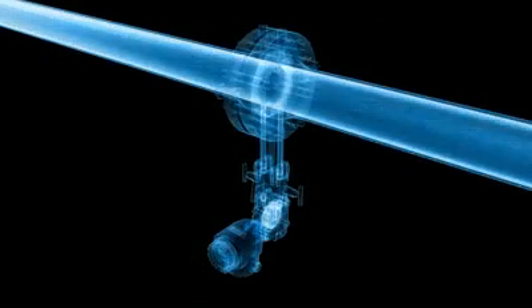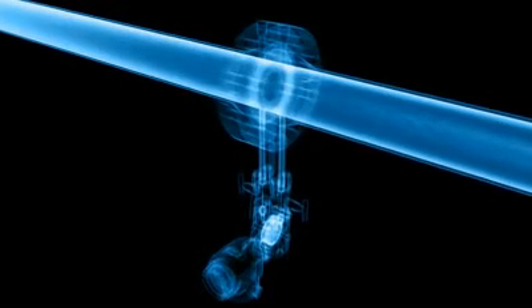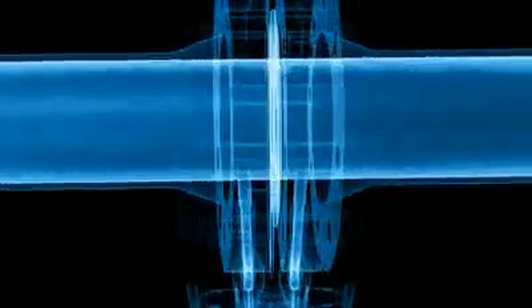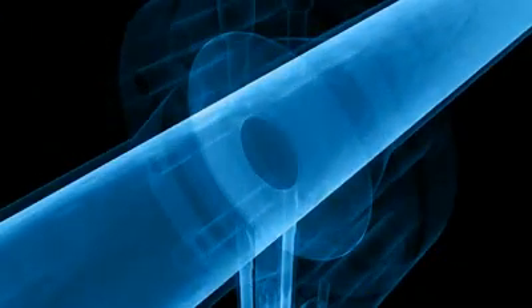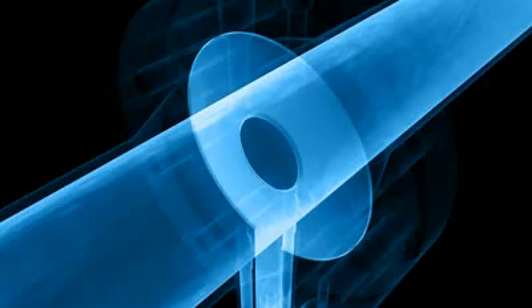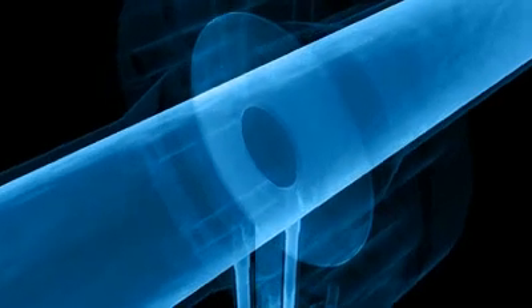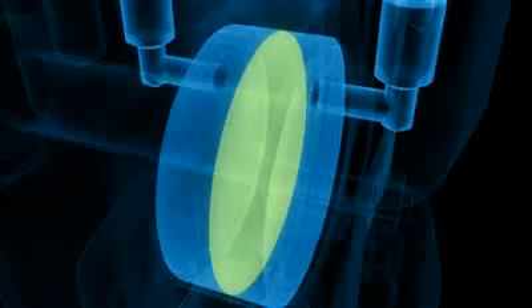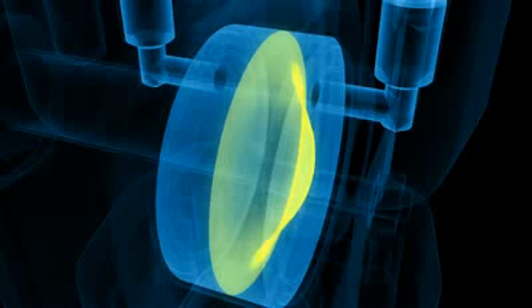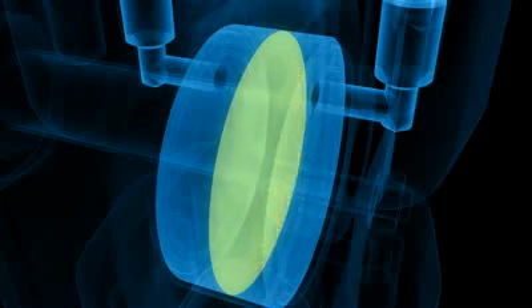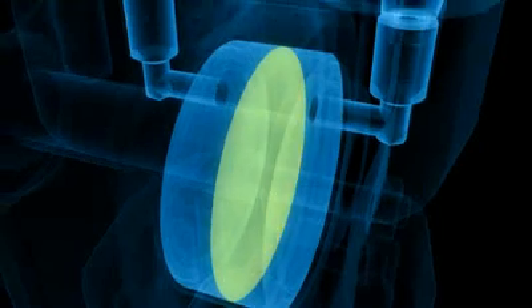Here is how this measurement method works. Differential pressure flow meters have an artificial restriction integrated into the measuring tube, illustrated here by the example of an orifice plate. Two holes are located in the pipe wall, one before and one after the orifice plate. Two separate tubes connect these holes to a differential pressure sensor, with its two pressure chambers, separated by a diaphragm. The tiniest pressure differences in the flowing fluid can be precisely measured.